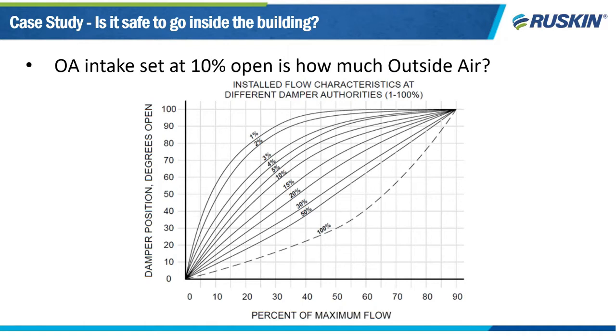This graph is showing a parallel blade damper with 100% authority would need to be 5% open to bring in 10% of its maximum flow. However, if the pressure drop across the damper is a very small percentage of the system's total pressure drop, then it might need to be open as much as 60% to bring in that same amount of air. The point I wanted to make is that damper position does not equate to the amount of airflow. Regardless of the way the outside air damper is controlled, manually in an older system or dynamically using demand-controlled ventilation, it's critical that the amount of outside air be established using other means.